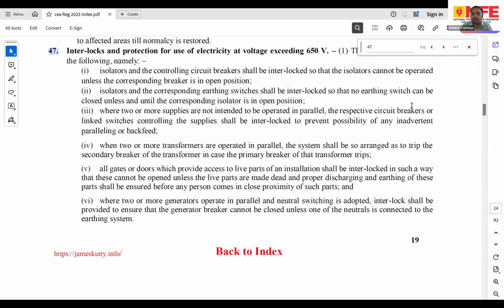Otherwise, in case the problem of harmonics is not so predominant in the system, the best practice would be just to have a common neutral bus, earth it, and don't have a switch neutral. The regulation specifically talks about scenarios where there is a neutral switching.